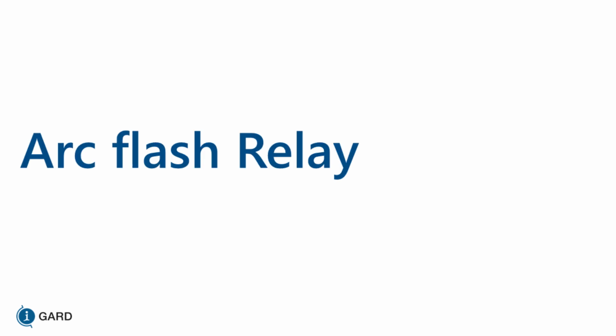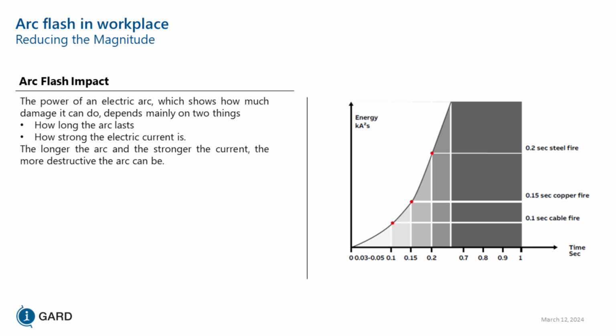So we had some customers that came to me and said, resistance grounded system, but I can't change the label. Why don't you develop something that allows me to put in the high resistance grounded system and be able to change the label? So we came up with an arc flash for that smart HRG system, which allows you to do just that.